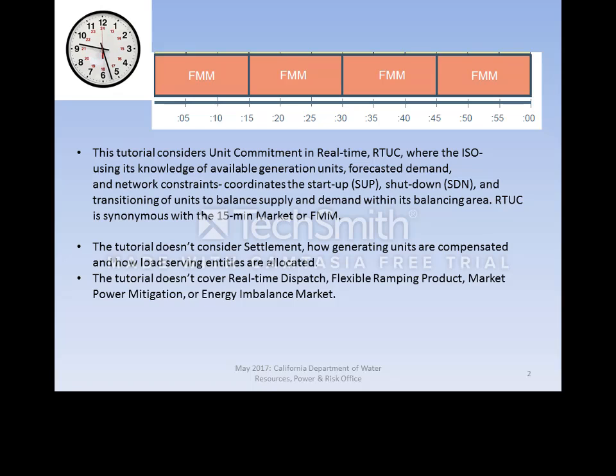The CAISO real-time market consists of multiple processes or applications which, in the words of the BPM, are multi-interval optimization functions minimizing the cost of dispatching imbalance energy and procuring additional ancillary services when applicable, subject to resource and network constraints. Think of imbalance energy as the difference between scheduled energy flows — for instance, the day-ahead market schedule — and the actual meter readings. The real-time applications use sub-hourly time intervals within their time horizon.